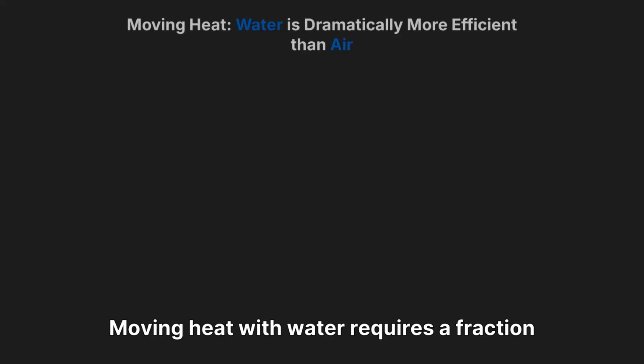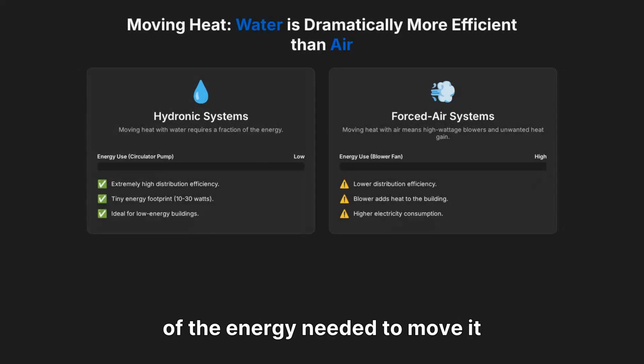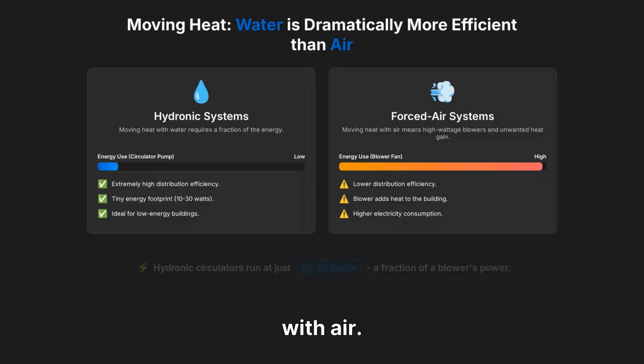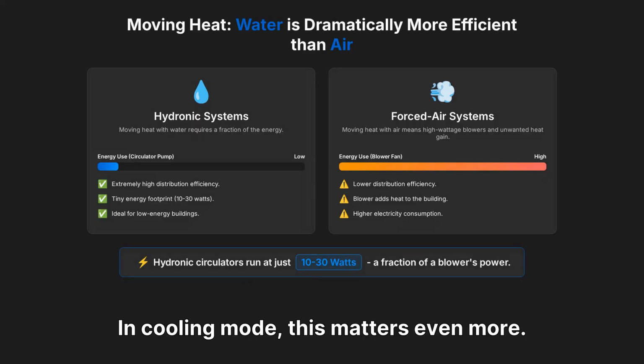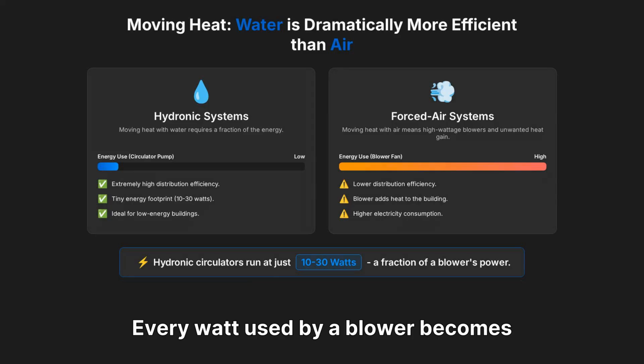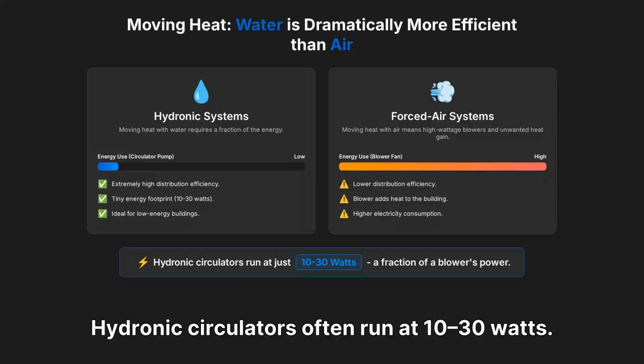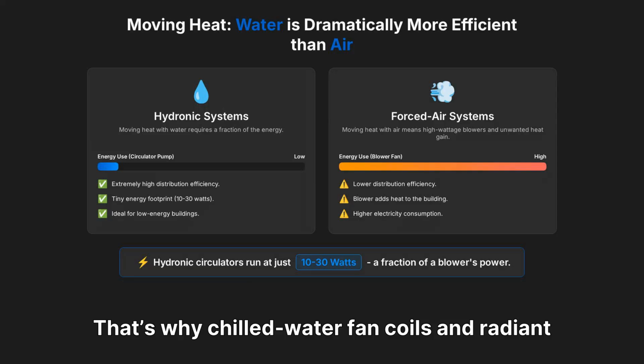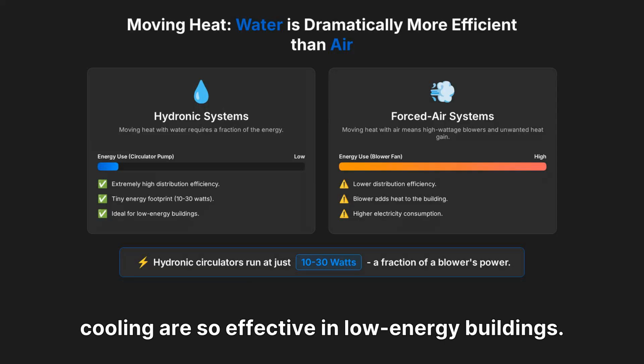Here's where hydronics really dominate. Moving heat with water requires a fraction of the energy needed to move it with air. In cooling mode, this matters even more. Every watt used by a blower becomes unwanted heat inside the building. Hydronic circulators often run at 10 to 30 watts. That's why chilled water fan coils and radiant cooling are so effective in low-energy buildings.